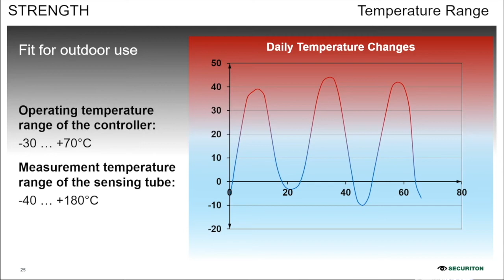We have a feature called Dynamic Heat Watch. Dynamic Heat Watch is one of the best features available in the industry of heat and fire detection. I tell you why, because this feature eliminates nuisance alarms and disturbance alarms. In the event of slowly and steadily increasing pressure values over a relatively longer period of time, which are not within the detection range, you already set a differential value.